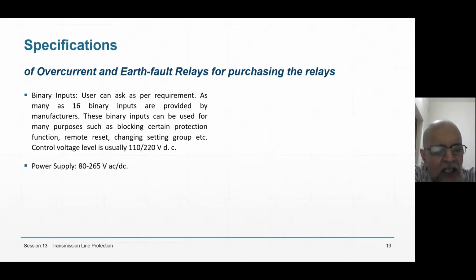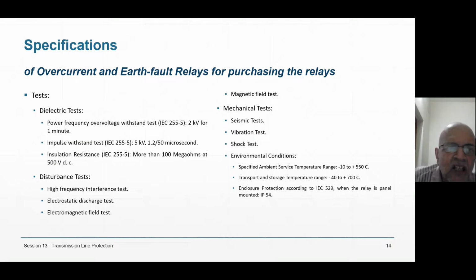The relay will be a locked out type relay. That means even if the current goes to zero, the relay will not reset. Self reset will not be there. Hand reset will be there. So many functions are available using binary inputs. Power supply for binary inputs is 80 to 265 volt AC/DC. So these are the specifications. Tests. You have to do tests. Whenever you order, you will have to say that you want to see so many tests.